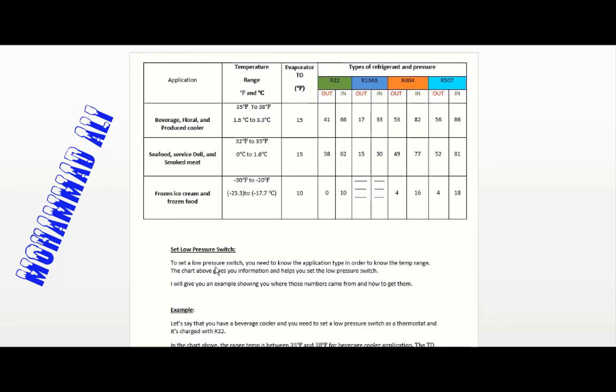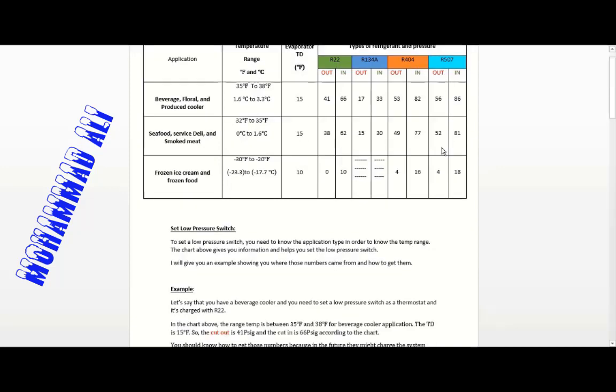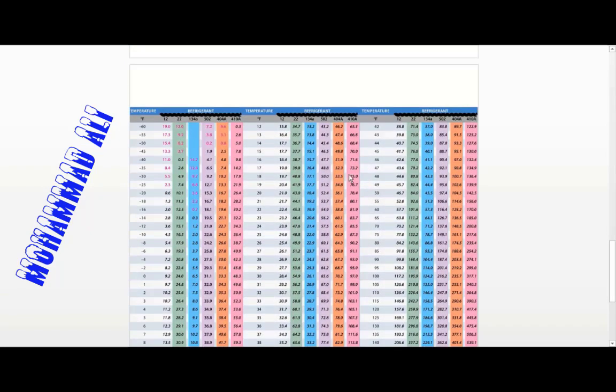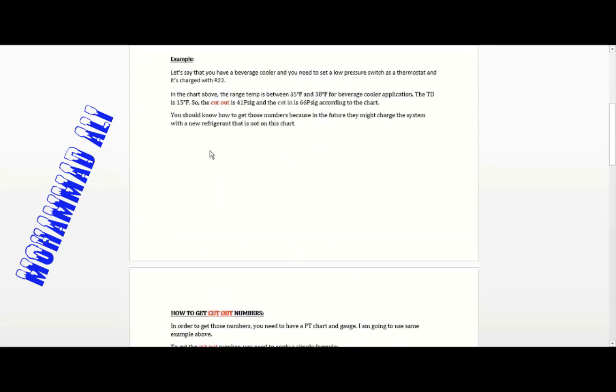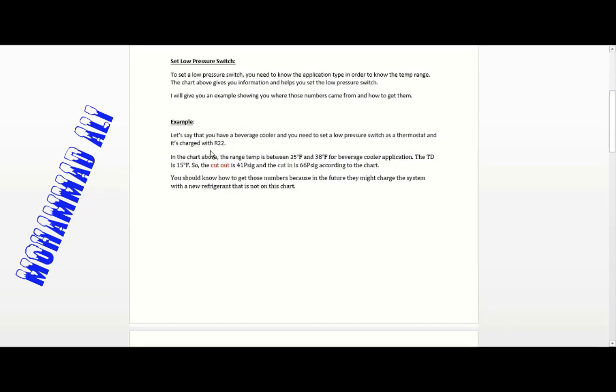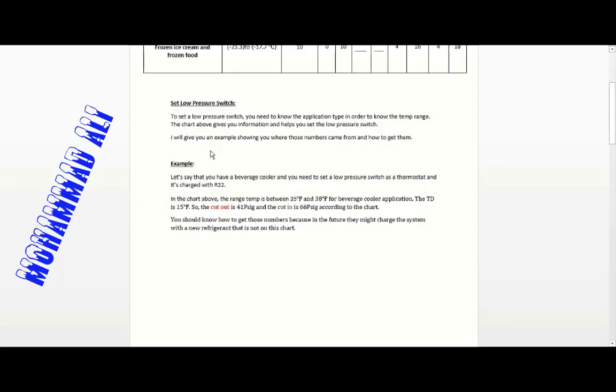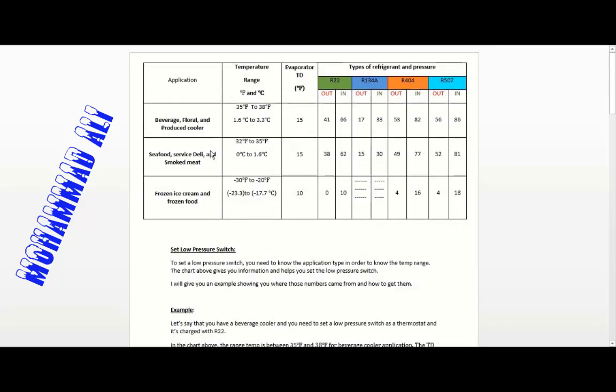To set the low pressure switch, we need to know certain things. I have a chart here showing application type, temperature range, TD temperature, and type of refrigerant. We also need a PT chart — sometimes called a TP chart. We're going to use gauges as well, because you don't want to rely on the low pressure switch needle pointer since it can bend or be inaccurate.